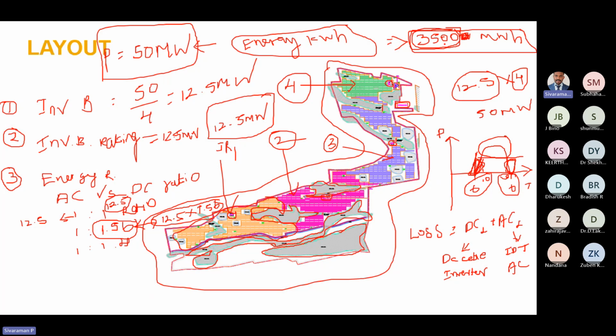For maintaining 3500 megawatt hour, the energy requirement is a minimum of 3500 megawatt hour. In order to get 3500 megawatt hour at the interconnection point, we have to consider the plant losses as well, both the DC loss and the AC loss. In the DC losses, the DC cable and inverter will come, and on the AC side, the inverter duty transformer, then the AC cable. If there is a transformer at the substation, and a transmission line from the substation to the interconnection point, those will also encounter loss, so we have to include those too.